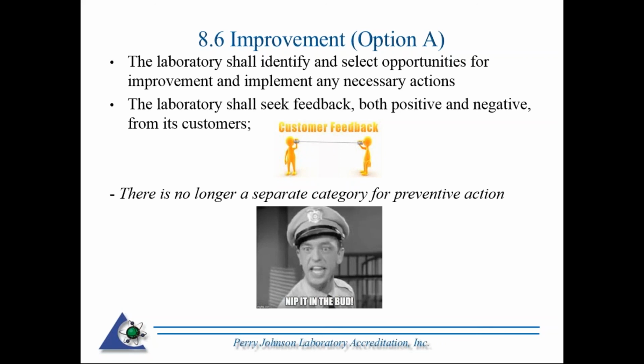Basically, the laboratory shall identify and select opportunities, and customers' feedback still needs to be pursued by the lab. No difference there. Another item that you don't see anymore is preventive action. That does not occur in the 2017 standard. Preventive action is being proactive, as our friend Barney Fife there says, nip it in the bud. So that's going to come under 8.6 under the section of improvement, but you don't see that term, preventive action, in 2017.